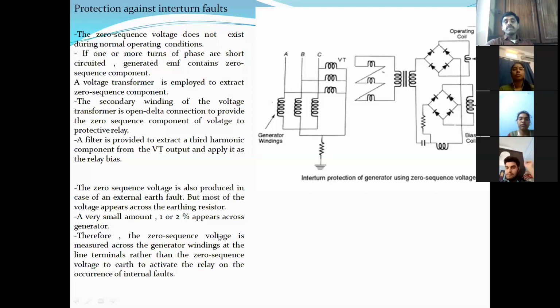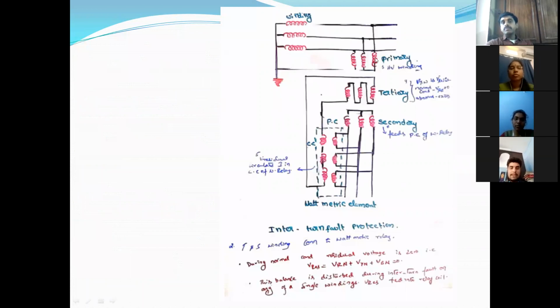So therefore, zero sequence voltage is measured across the generator windings at the line terminals rather than zero sequence voltage to earth, to activate the relay on the occurrence of internal faults. That means this scheme is majorly employed to identify the zero sequence voltage whenever there is a turn to turn fault. And the last scheme for interturn fault is the wattmetric relay. Here you can observe there is a generator winding. There is a 3 winding transformer: primary, high voltage winding, tertiary winding, and secondary winding. Here the voltage across the tertiary winding is the residual voltage.